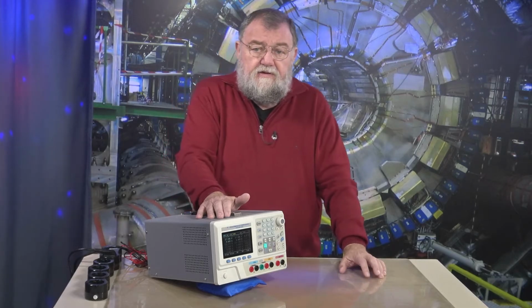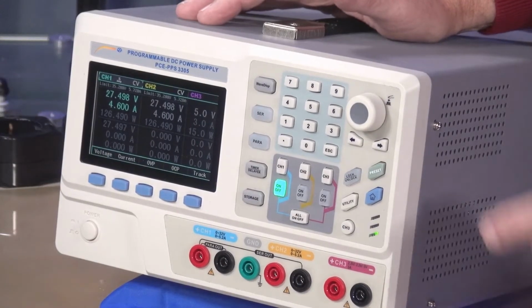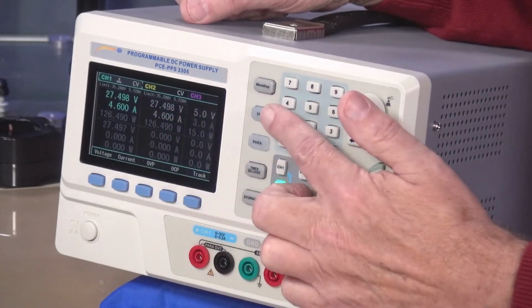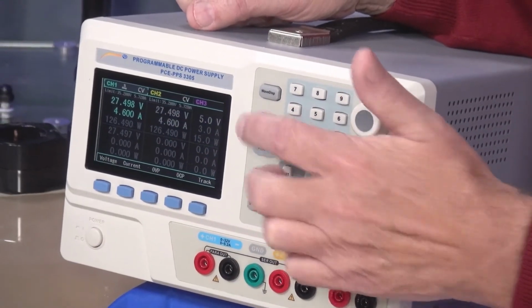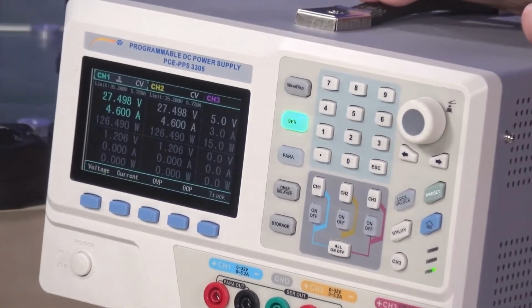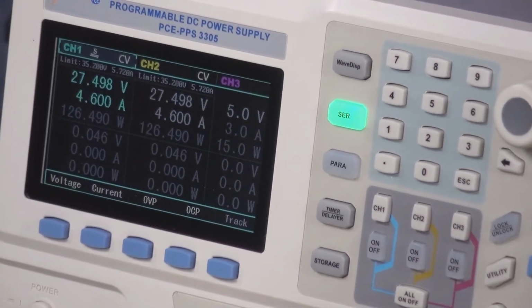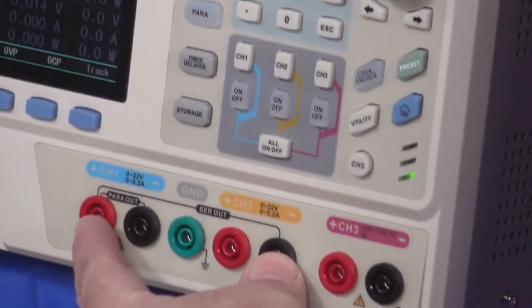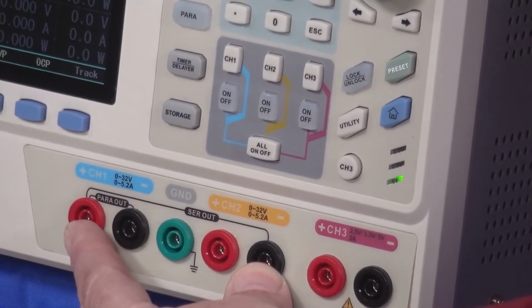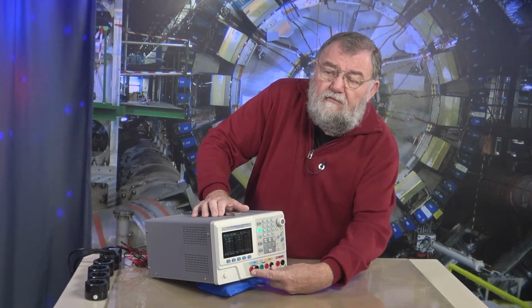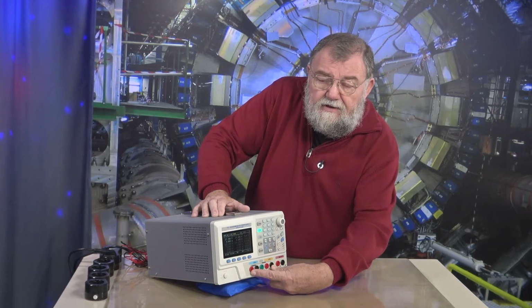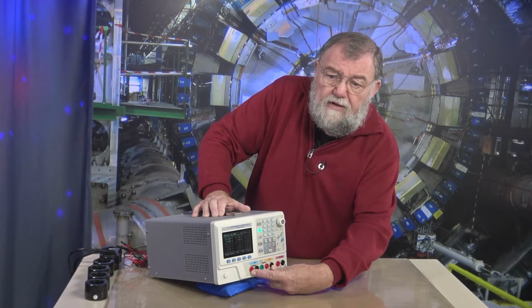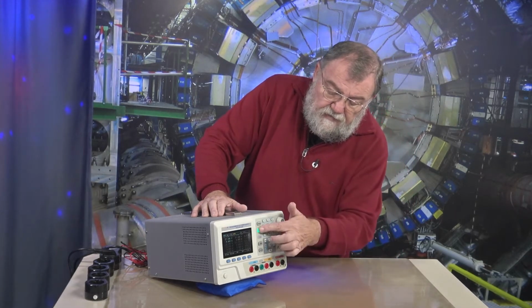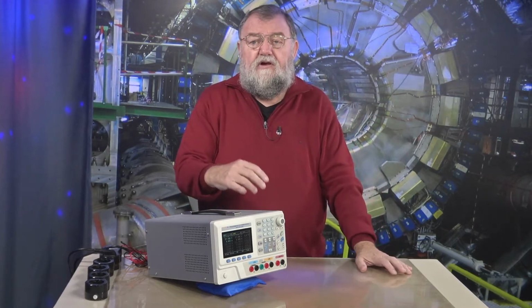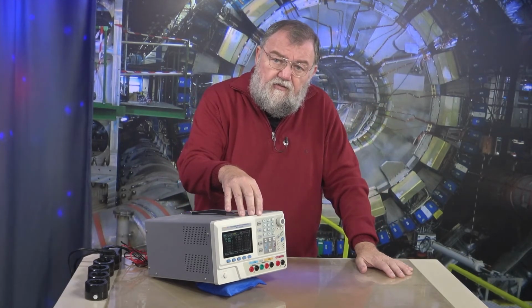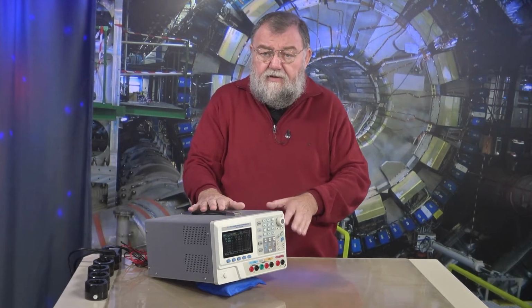That makes sense, but in that case I switch to serial operation. With serial operation, both outputs are switched in a row, so I can take the addition of both channels, which are always identical. That means I only need to take the display value times 2 and don't have to calculate. The same goes for parallel switching with current, so instead of 5.2 amps I get 10.4 amps.